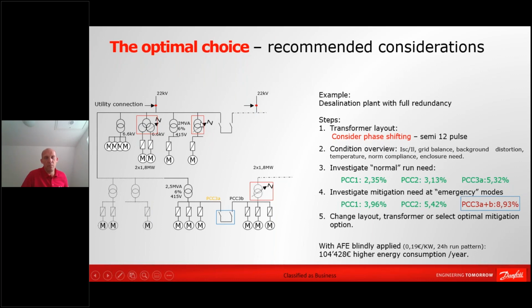You can do the same for some of the other installations where you simply, because of the angle changes, can actually phase shift the transformer or the harmonic angles so that they are compensating out each other, and that will improve your situation. And it doesn't cost you anything because the transformer is needed anyway. So it's a cheap way to reduce harmonics if you have the ability to actually consider these moves already upfront.